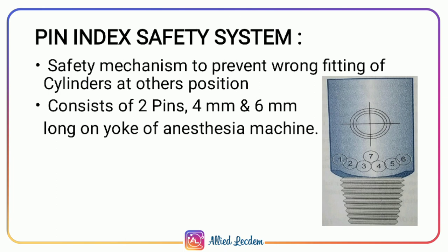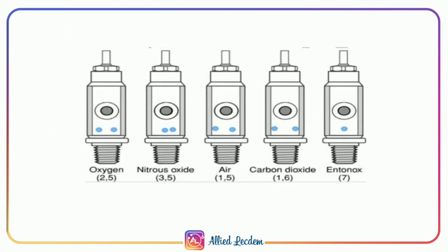The pin index safety system is a safety mechanism preventing wrong fitting of cylinders into other positions or ports. It allows only specific gas cylinders to be attached to their designated port. The system consists of two pins — 4 mm and 6 mm long — on the yoke assembly of the anesthesia machine. To understand this: imagine a charger as the cylinder and the plug point as the hanger yoke assembly. The pins are present on the yoke of the anesthesia machine, and the corresponding holes are on the cylinder.